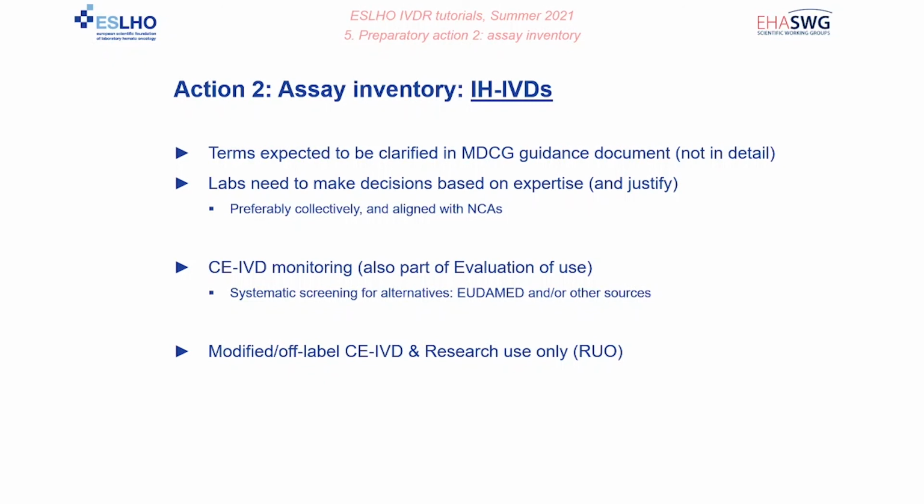Then concerning the need to look for equivalent CE IVDs and to compare them with your in-house devices, based on Article 5.5d. Since manufacturers will need to submit information on their medical devices to EUDAMED, the European Databank on Medical Devices, this database will be the designated place to perform such CE IVD monitoring. However, the number of CE IVDs that have been certified under the IVDR is very limited so far, and also EUDAMED is not functional yet. That means that at present, it is not straightforward to search for available alternatives for your in-house devices.